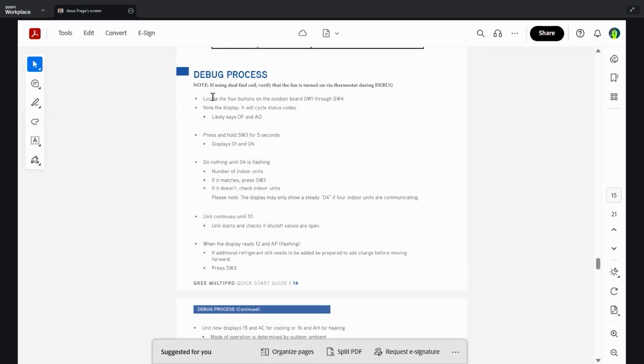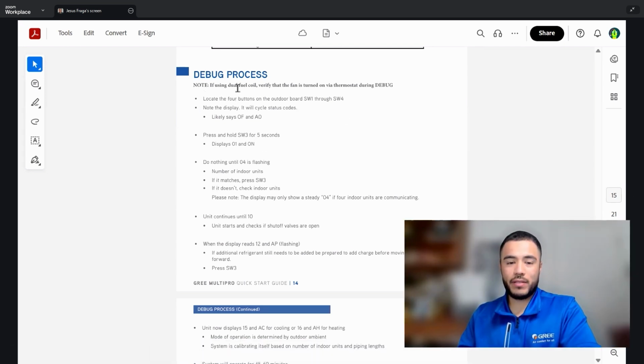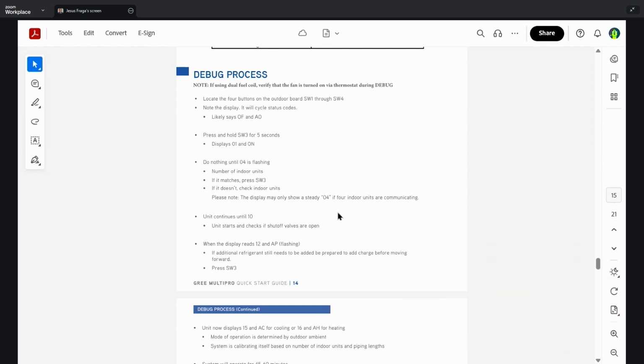The debug process, pretty much it's the same as the 410A. So we know that once we have the system piped together, pulled a vacuum, and we're ready to do the actual start, this is after we've released the charge and added any additional refrigerant if needed. We're going to go ahead and verify that the outdoor unit says AO along with the indoor unit and its wired controllers. So everything in the system from the outdoor unit to the indoor units should show an AO.